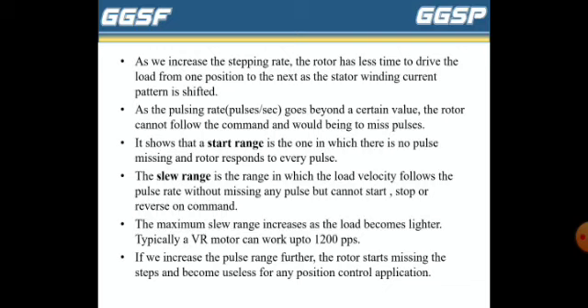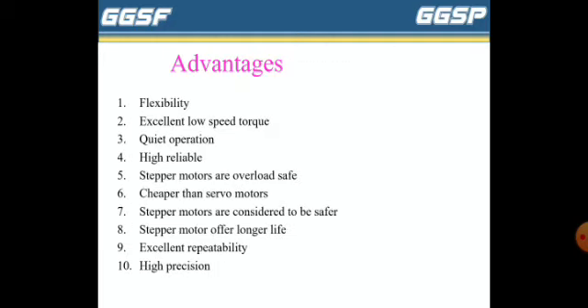If we increase the pulse rate further, the rotor starts missing the steps and becomes useless for any position control application. Advantages of the stepper motor are flexibility, excellent low speed torque, quiet operation, and high reliability. Stepper motors are overload safe. They are cheaper than servo motors. They are also considered to be safer and have longer life. They operate excellently on repeat and have high precision.